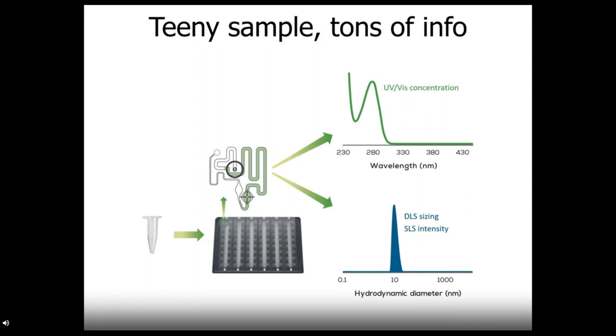Stunner combines UV-Vis for concentration and DLS for sizing. SLS intensity data is also read during a DLS experiment. So low-volume, high-throughput DLS to get the size and PDI data you need, while quantifying DNA or RNA concentration. All this is done in a 96-well plate-based format that powers high-throughput analysis, giving you all this data on 96 samples in one hour.